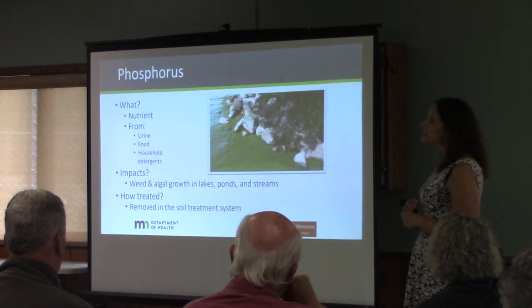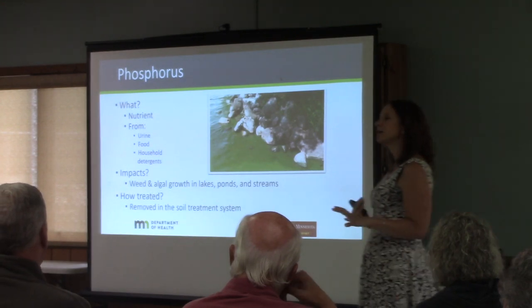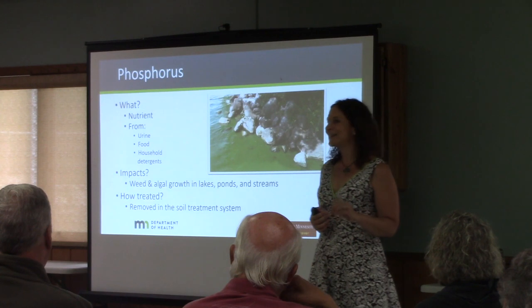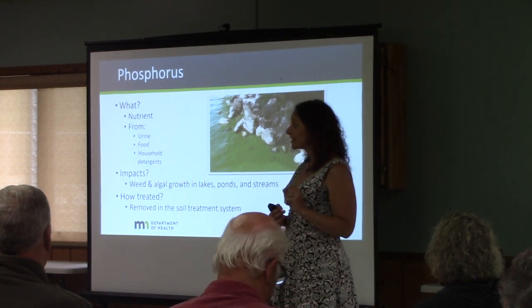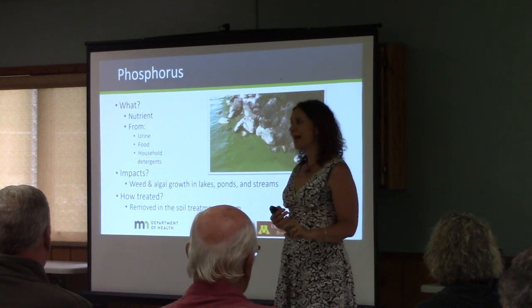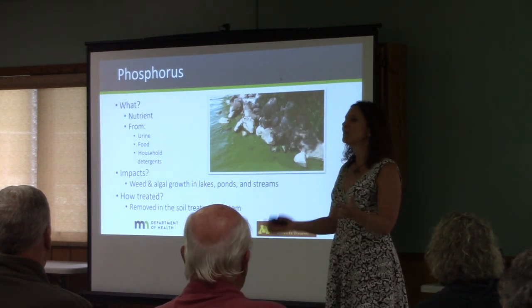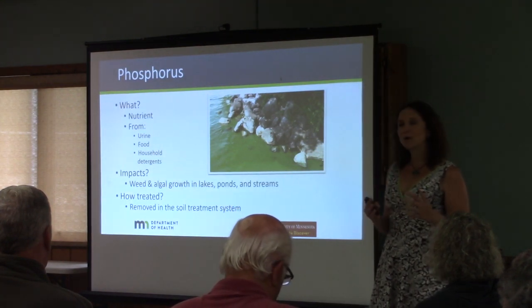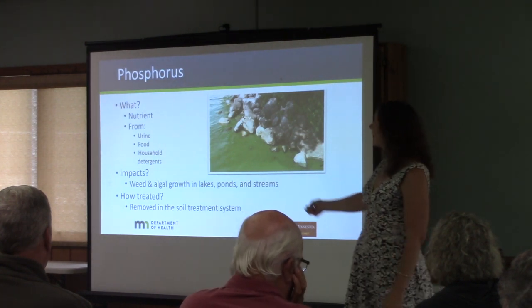All right, so phosphorus. Phosphorus is the number one reason when you see a pond or a lake that's green. I do want to highlight that not all the phosphorus comes from septic systems. A lot of it comes from fertilizer, it comes from ag runoff, all kinds of sources, but whenever I get in that discussion with people, I want our septic systems to be removing their phosphorus. And the number one way we remove phosphorus is having 3 feet of soil.